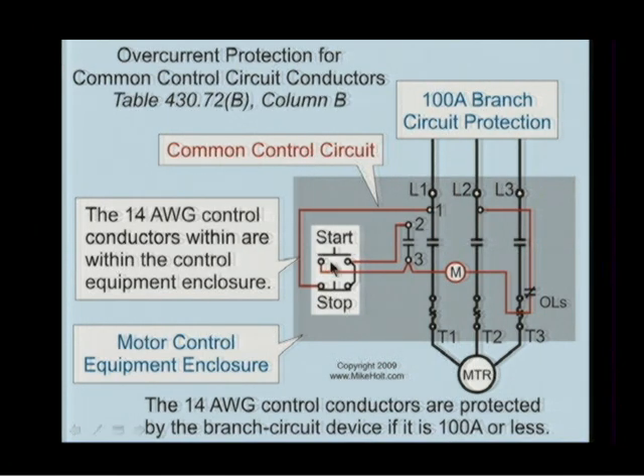Now, what size wire do you typically use for your controls? Well, I hasten to reiterate that this is for tapped control conductors that are directly off the branch circuit. And I'm glad you brought that up. We're not talking about fuse protection. We're just saying, hey, listen, you're tapping off of control conductors, and there is no overcurrent protection for those tap conductors. You're using the branch circuit, short circuit, ground fault protection device to protect those tap conductors. So therefore, there's a limitation on the tap conductors. Do you typically provide protection of your tap conductors? Well, we don't have tap conductors per se because we have 480 volt motors and our control conductors come through a transformer. So it's a different section. All right, so then right now we're not going to get involved in what you're doing.